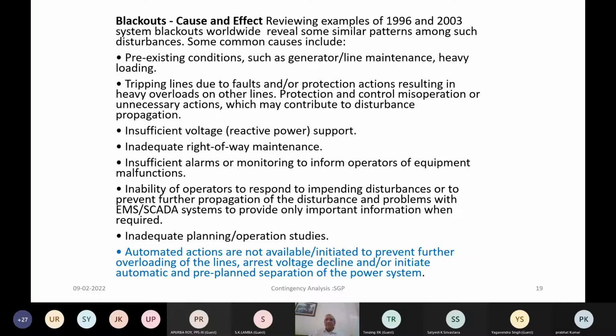So there is a long pre-existing condition which has depleted the transmission system, and then some forced outages happen due to fault, etc. So this results again in a disturbance which can lead to grid collapse. Next is insufficient reactive power support. We talked about the need for reactive support, but if the support is insufficient, there can be voltage instability by the voltage collapse phenomenon, and we had discussed at length the power versus voltage curve of the transmission line. So this is another common cause.